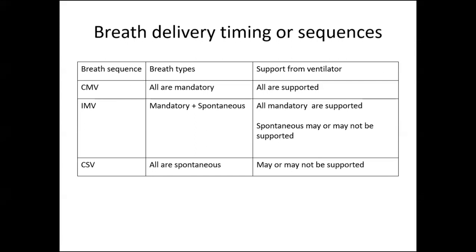IMV has mandatory and spontaneous breaths. All mandatory breaths again get support from the ventilator. Whether spontaneous breaths get support from the ventilator or not depends on your choice. It's not the ventilator's choice. If you want to support them, you can, and your support should never be equal to that of the mandatory breath. If you do that, there is no difference between CMV and IMV.